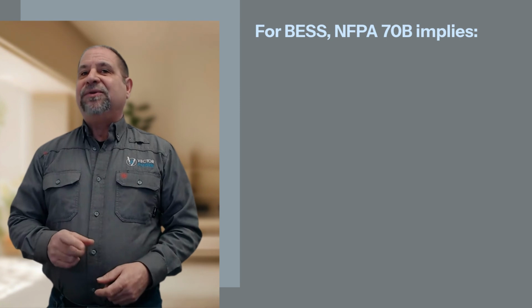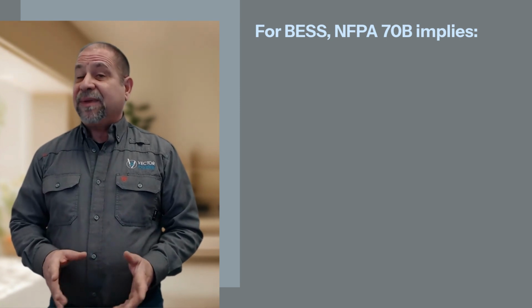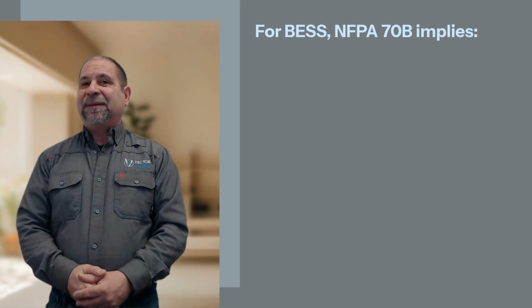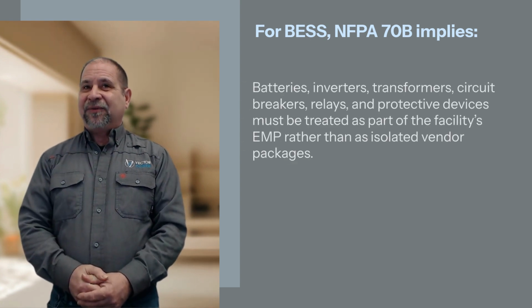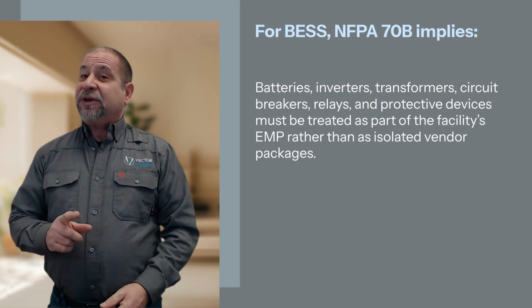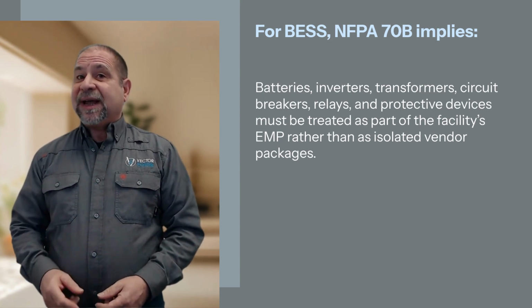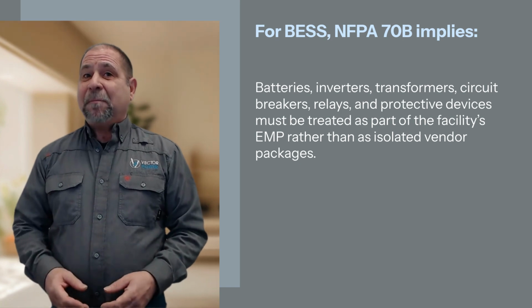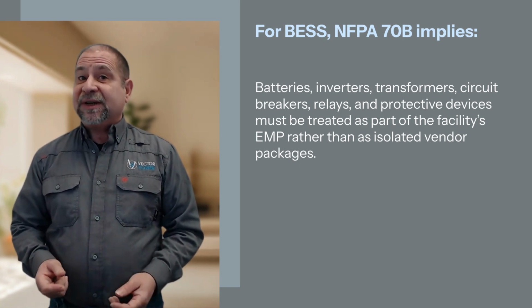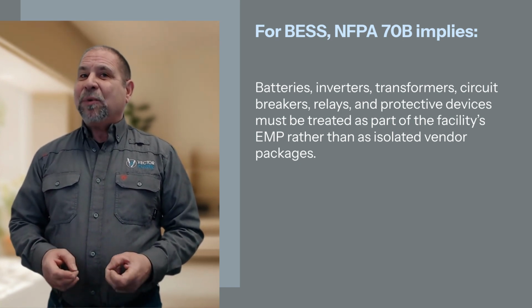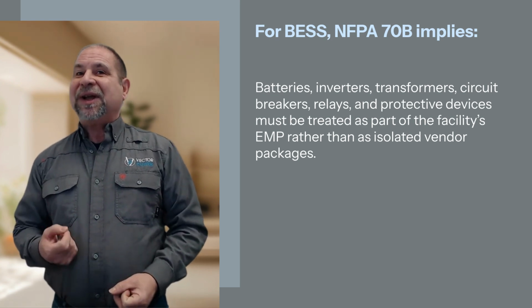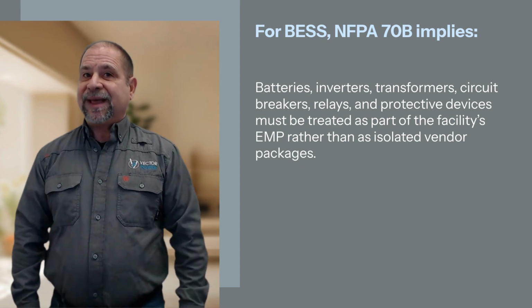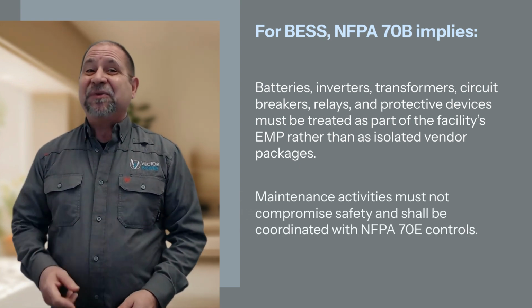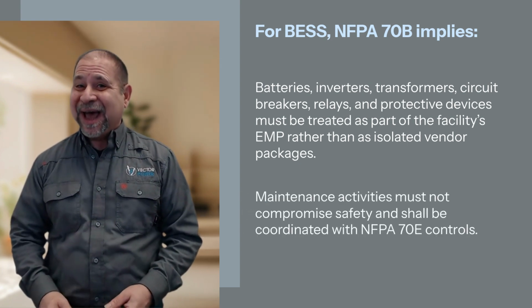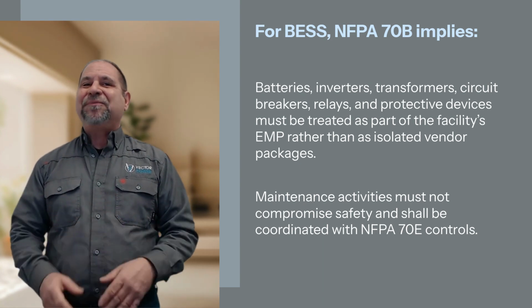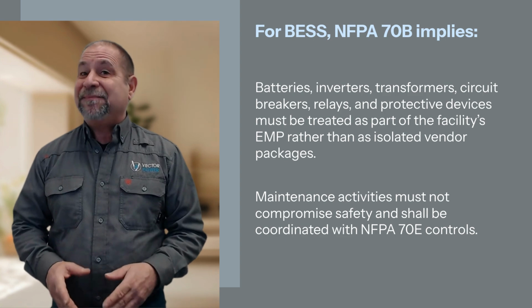For battery energy storage systems, NFPA 70B implies batteries, inverters, transformers, circuit breakers, relays, and protective devices must be treated as part of the facility's electrical maintenance program rather than as isolated vendor packages. Maintenance activities must not compromise safety and shall be coordinated with NFPA 70E controls.